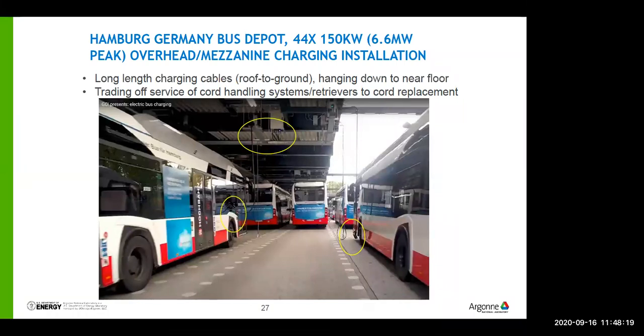This takeaway slide talks about their choice not to have cord retrievers, because if the utility is paying for half or all of the charging installation, maintenance becomes an issue. The thin cords are for communication and monitoring, basically accessory power for the buses when not in use. The black cable hanging near the wheel in the lower right is the charging connector, shown on the left plugged into the vehicle just above the wheel next to the entrance door. Their philosophy was it's cheaper to replace cords torn off by people snagging on the mirrors than to replace cord handlers, which they believe will jam. So there are a lot of trade-offs, but that's a big issue around maintenance.